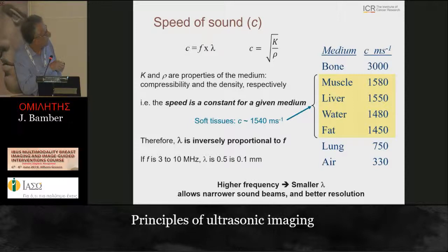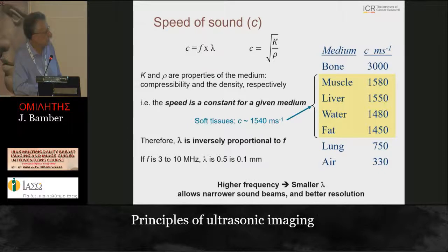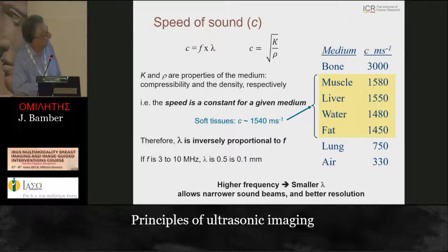From the equation, wavelength is inversely proportional to frequency. The higher the frequency, the shorter the wavelength, and that's important for resolution - it's why higher frequencies give better resolution, because smaller wavelengths can be focused more easily. If frequency is 3 to 10 megahertz, the wavelength is of the order of 0.5 to 0.1 millimeters. The higher the frequency, the smaller the wavelength, allowing narrower sound beams and better resolution.